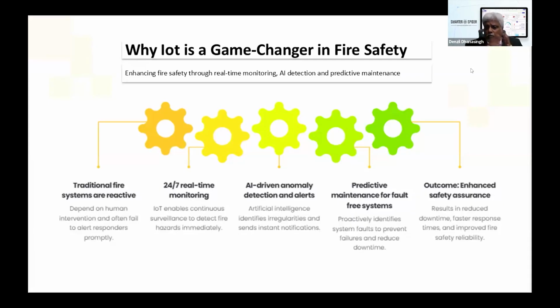We ensure this, and also the prediction of false alarms. You'll have a maintenance team, or an annual maintenance contract with some company. If you send them an alarm, they'll know it has come and rectify it. But if they don't take action, it will remain idle and you won't know. So using our intelligence, the system escalates to the next level, to the manager, saying this fault has existed for more than a day, two days, or 48 hours, whatever it is. We can program it per requirements, and ensure the manager asks the maintenance team to rectify it.